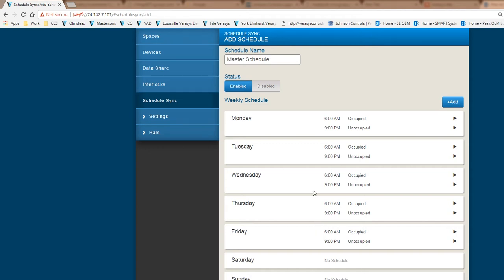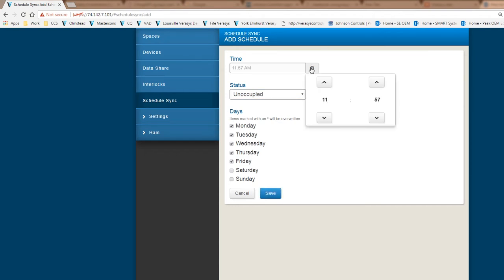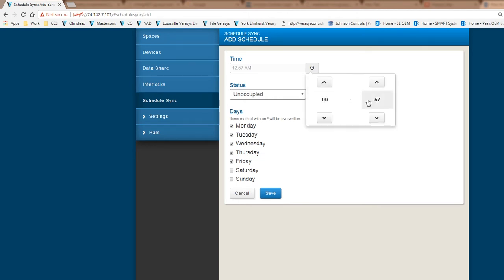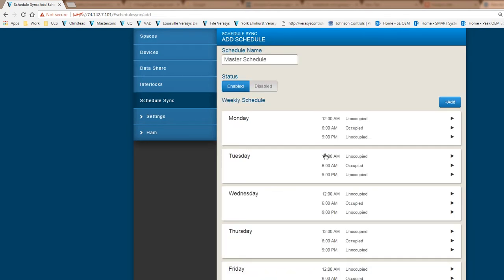Within our documentation or user guide documentation we do explain how to do this, but one area that is a little bit unknown, something you have to know, and this is due to the BACnet object that we're using. We're correcting this in the next revision, but for version 1.0, one other step you have to do is to add another unoccupied time for the period Monday through Friday right at midnight.